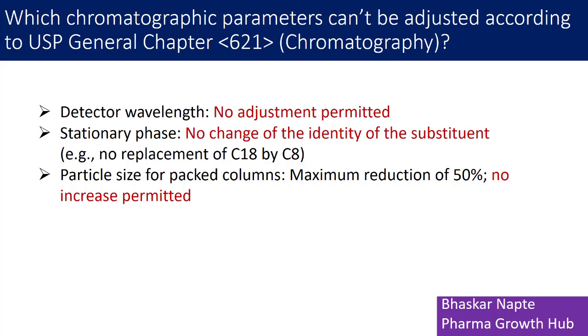The reason an increase in particle size is not allowed according to USP General Chapter 621 is that increasing particle size compromises surface area. If the surface area is reduced, the interaction of the analyte with the stationary phase is reduced. This reduced interaction results in poor retention and poor resolution, which is unacceptable chromatography. For that reason, an increase in particle size for packed columns is not permitted. Thank you so much.